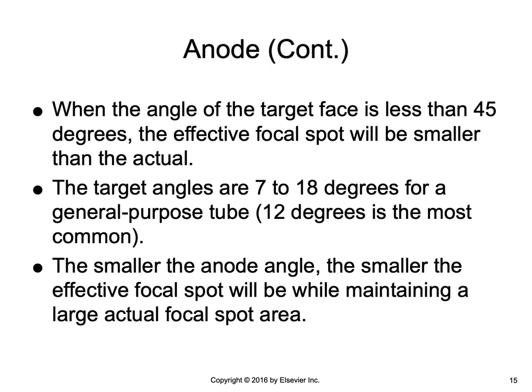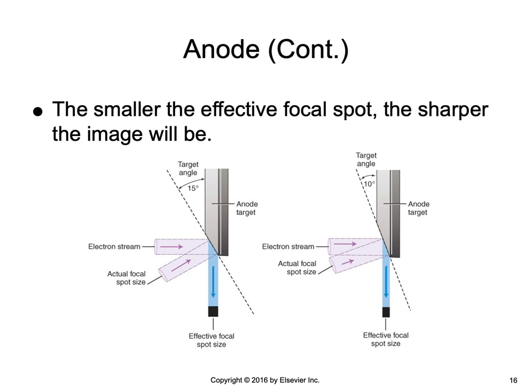When the angle of the target face is less than 45 degrees, the effective focal spot will be smaller than the actual focal spot. The target angles are 7 to 18 degrees for general purpose tubes, with 12 degrees being the most common. The smaller the anode angle, the smaller the effective focal spot while maintaining a large actual focal spot area — meaning a large actual focal spot for heat dissipation is maintained, but a small effective focal spot to improve image quality is created. The smaller the effective focal spot, the sharper the image. It should be noted that anode target angle is determined based on the intended use of the tube and is not something the radiographer selects at the operating console; for example, the angles are optimized for mammography units, angio units, general radiography units, and so on.